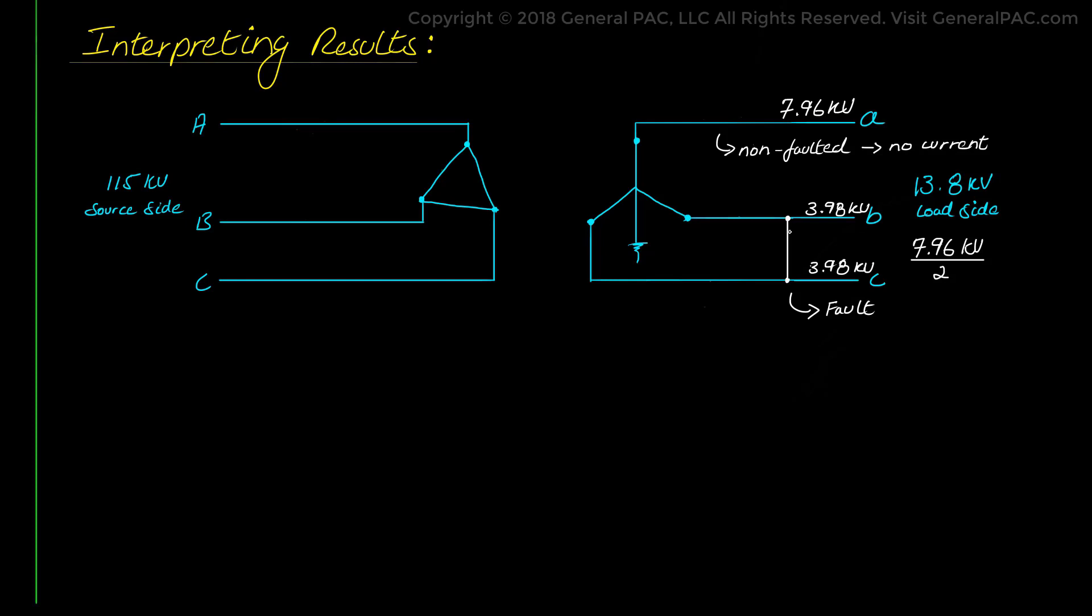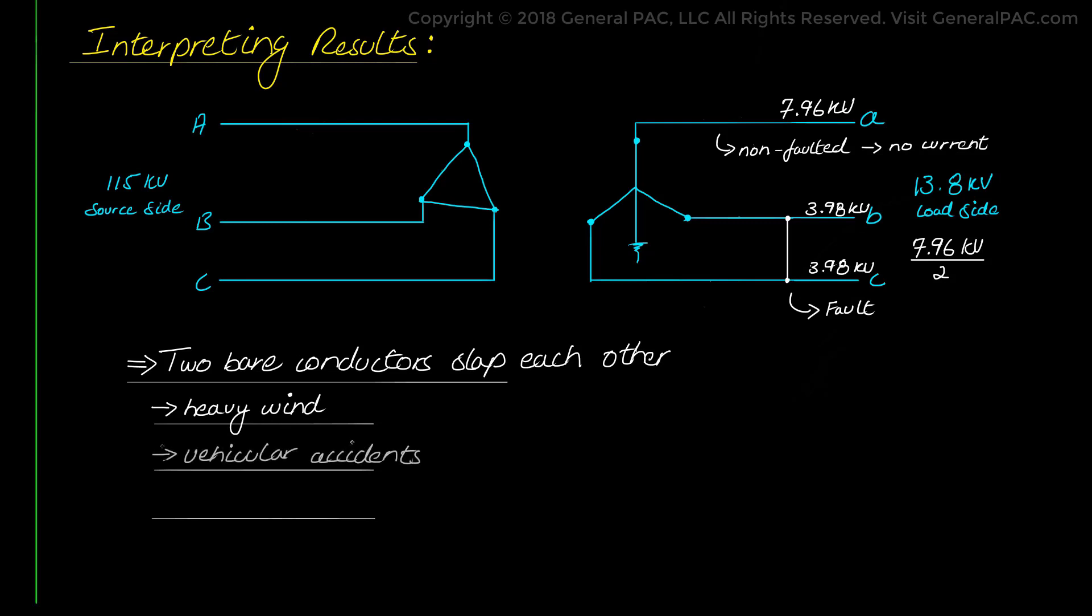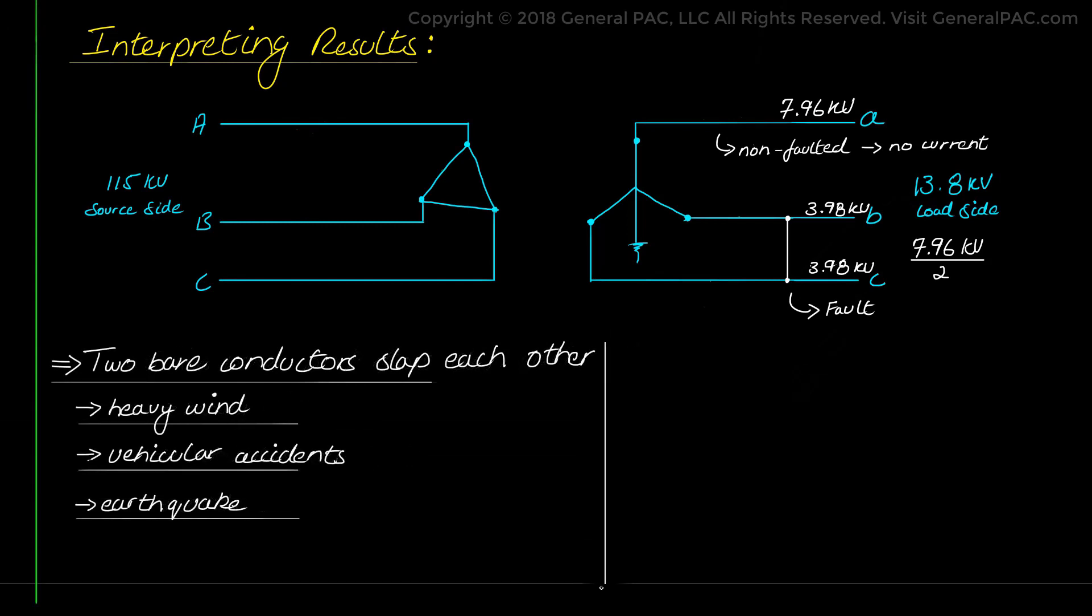Most notably, these types of faults occur when two bare conductors or phases slap each other due to like a heavy wind condition or a geo-disturbance like accidents, vehicular accidents on a pole where the bare conductor transmission lines are strung, or a small earthquake that causes these conductors to go back and forth and eventually slap each other. When that happens, it is a phase-to-phase fault.